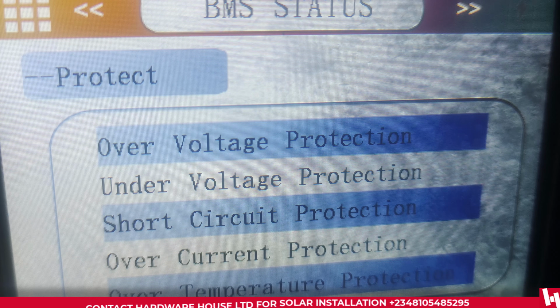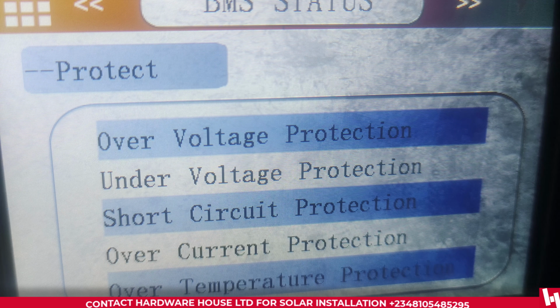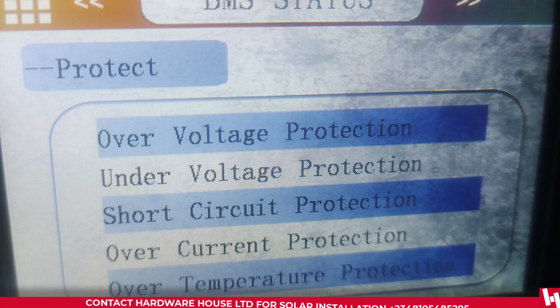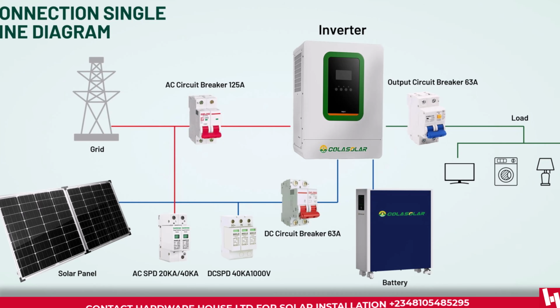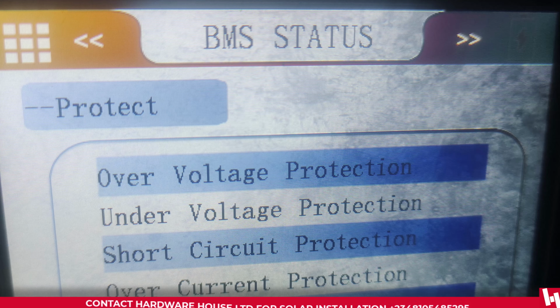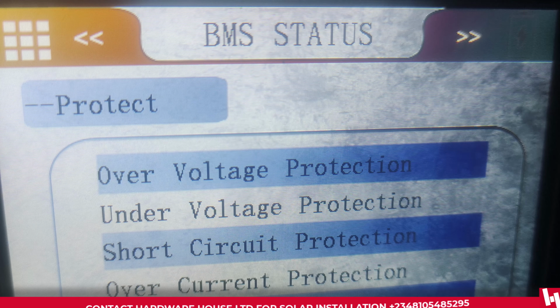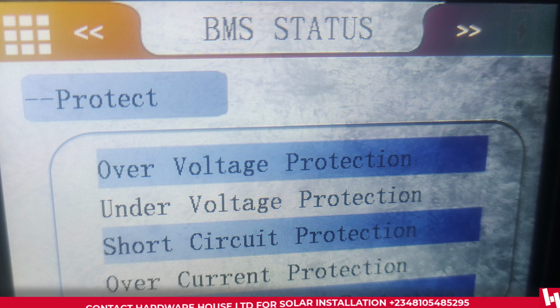Before any of this system will even be put to work, that means the inverter must have failed from the power management system aspect, and then the surge protectors must have failed, which is the mechanical switch, which is meant to detect surge and flip. So that is why this system is very much fail-safe. And there is also overcurrent protection, which can come from the charge controller that is inbuilt into this inverter system. If it's not able to regulate the current to voltage balance coming from the panel very well, and it somehow sends too much current to the battery, the battery management system is going to shut down and protect the battery.